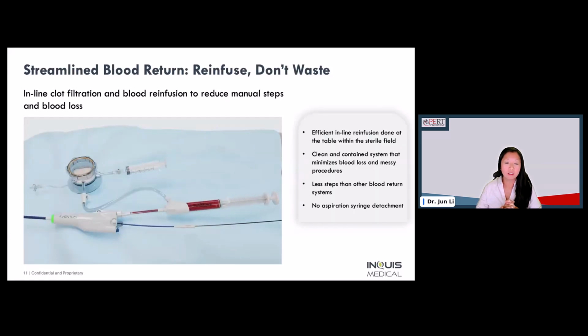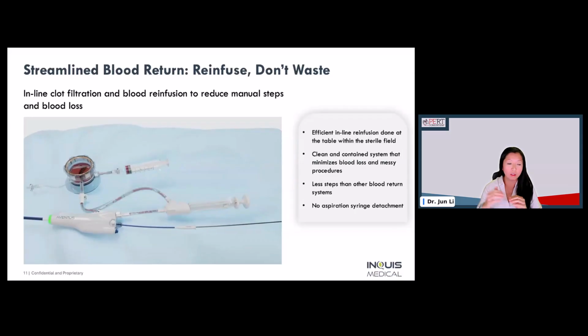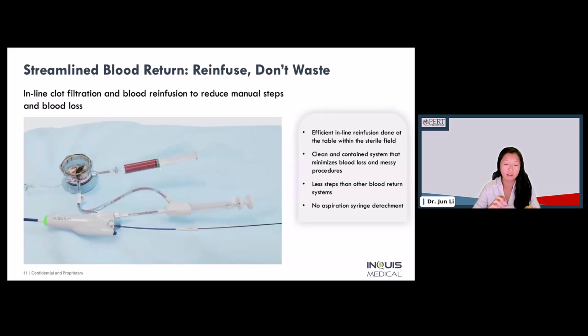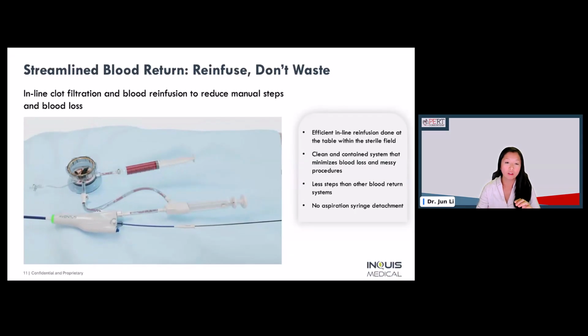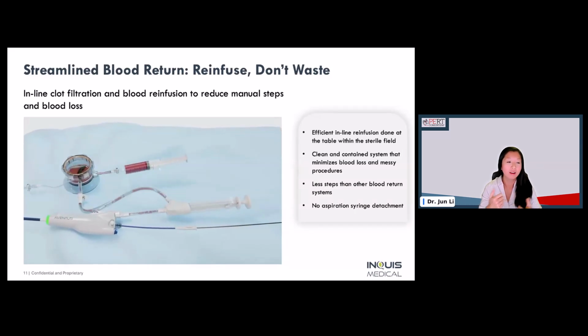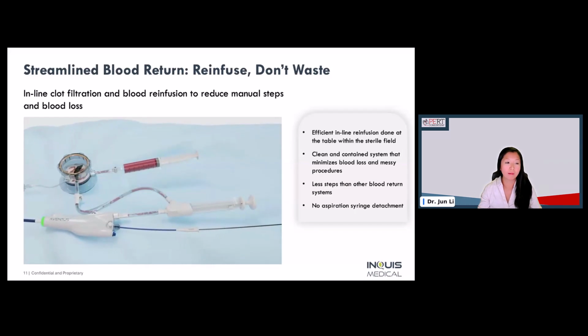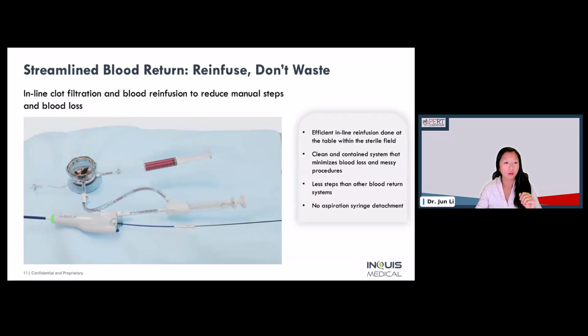One of the advantages that I've seen personally is that when you advance the catheter, you'll notice some changes in the color. As you advance, sometimes you'll pass the clot, and the light indicator will turn orange. You can do your aspiration, and as you do your aspiration, the light will turn green. And then sometimes if you are wall latched, what you can do is turn the catheter a little bit, essentially to free it from the wall so that you're not actively sucking down on the wall. So it really tells you a lot about your thrombectomy and how you're doing.